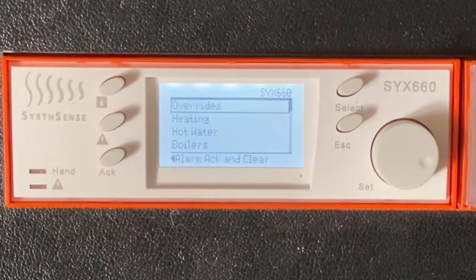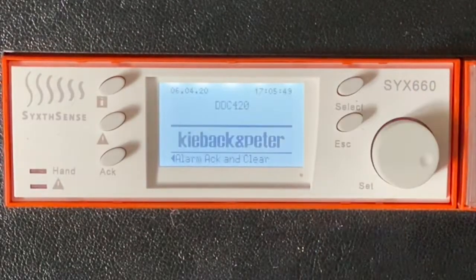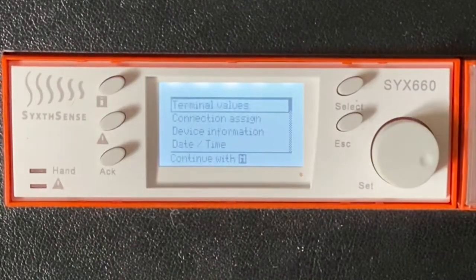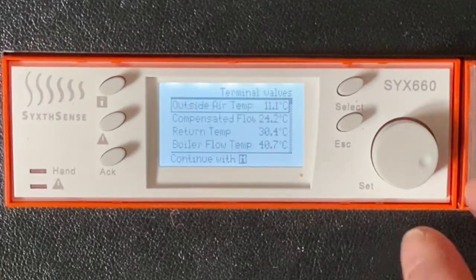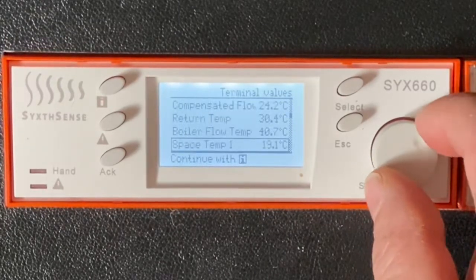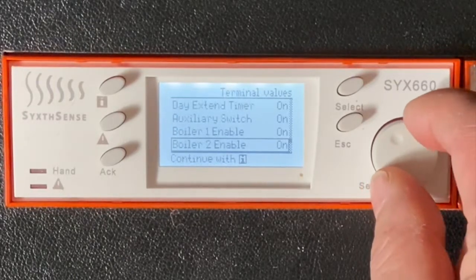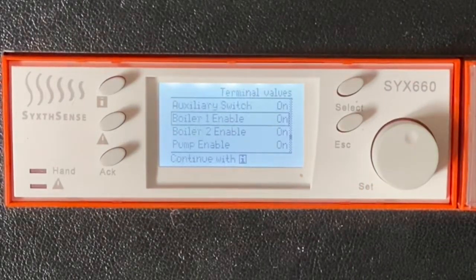So the first thing I'd like to touch on would be just to escape out of the product, get back to the time and date, where we have the information button. We can press on the information button and choose terminal values, and this gives us a live display of all of the inputs and outputs on the controller, so we can identify if, for example, a particular item of plant isn't working. It could be a wiring issue, it could be a power supply issue, it could be a piece of equipment issue, but if the controller is asking it to run but the plant isn't actually running, you can focus your attention onto the item concerned rather than focusing too much on the controller.